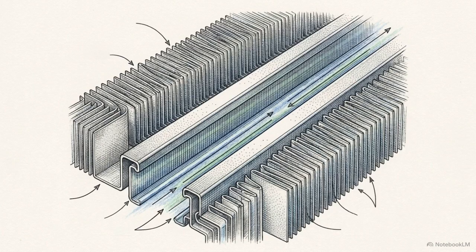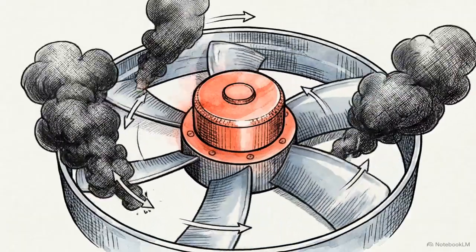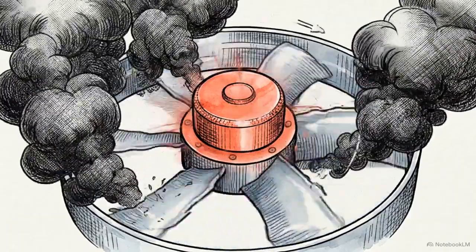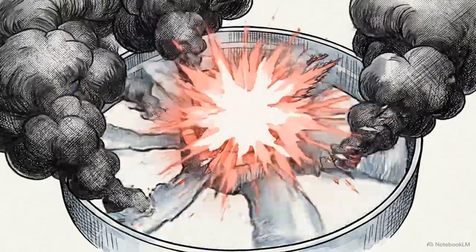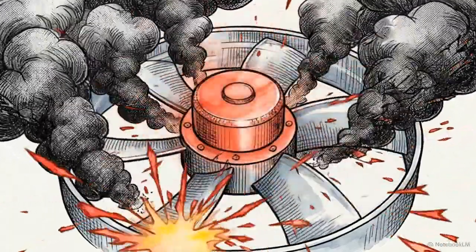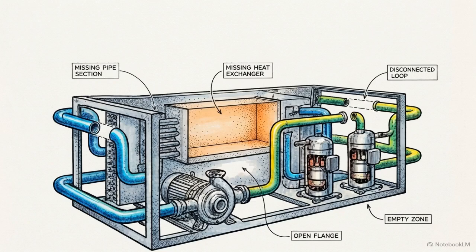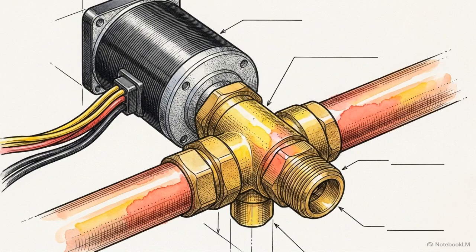This strict 60 kilowatt requirement dictates the selection of a microchannel condenser and sets the precise airflow volumes required from the external exhaust fans. Failing to account for the physical work of compression mathematically guarantees that your fans will be undersized, leading directly to catastrophic system overheating. Our core heat transfer loops are complete, but in their current state, the system lacks dynamic stability. We integrate an electronic expansion valve to rapidly regulate the refrigerant superheat as ambient conditions shift.